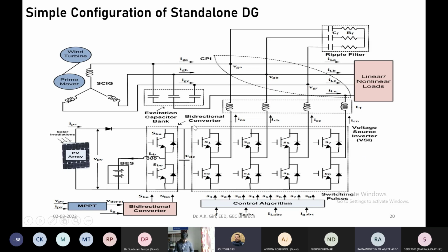This is basically a 4-leg converter, since we are addressing a 3-phase 4-wire system. The 4th leg addresses neutral current compensation, while the other three legs address phases A, B, and C.